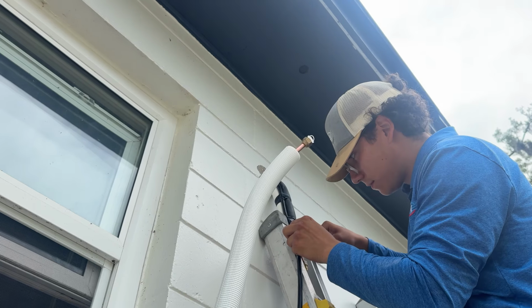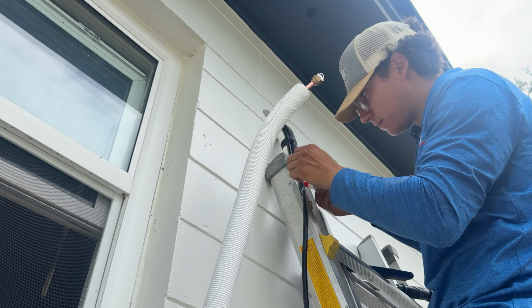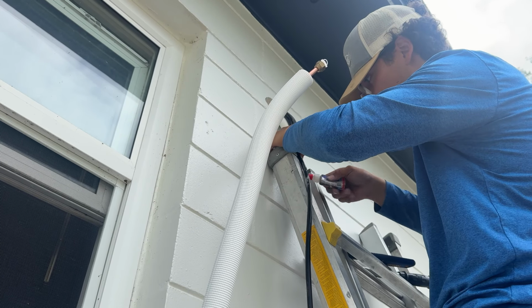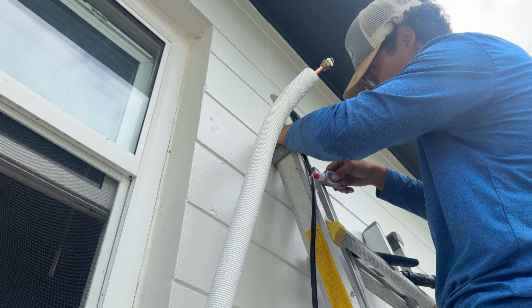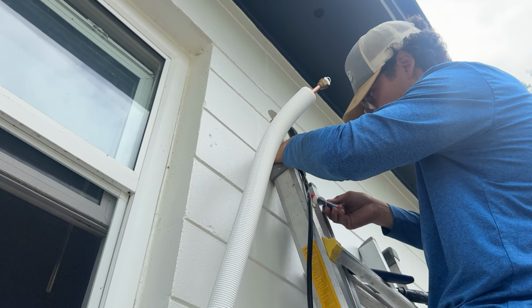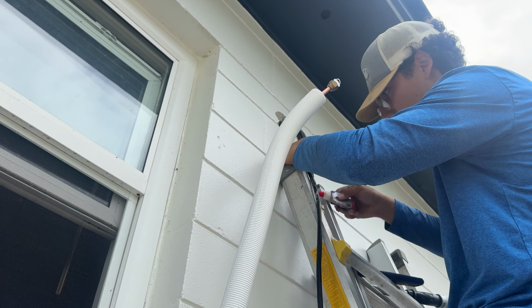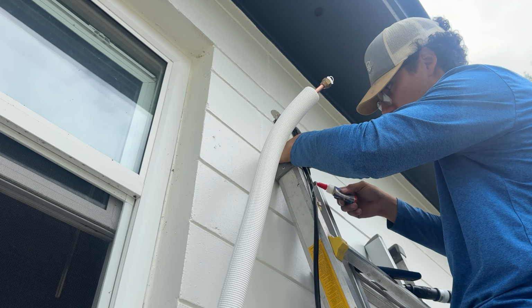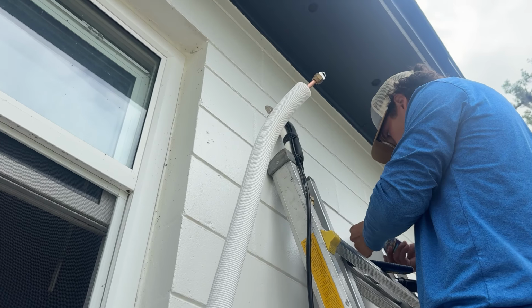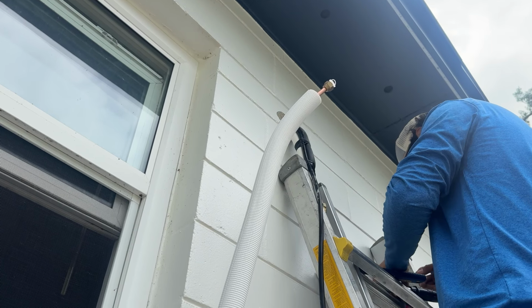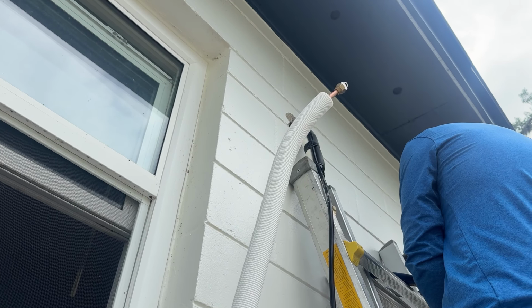And we have our first 3/8 connection. We want to limit the amount of exposure that those caps are missing from that indoor evaporator lines, because we don't want any of those non-condensables, the moisture, atmosphere, all that humidity to get in there, because that's going to increase our time to vacuum down once we have all of our connections in place.